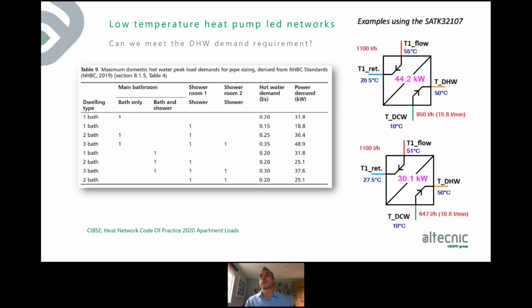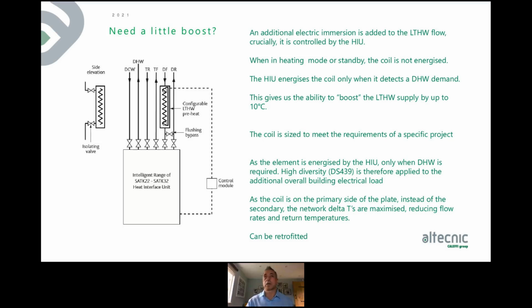So what do you do when you get to that situation where you need a bit more output from the unit? You can't go below that 1 degree approach, of course, otherwise the plate heat exchanger just won't effectively work. So what do you do? Well, that's where we come in with this. This is an immersion cylinder. It's like a tube, if you like, which sits onto the primary feed into the HIU.